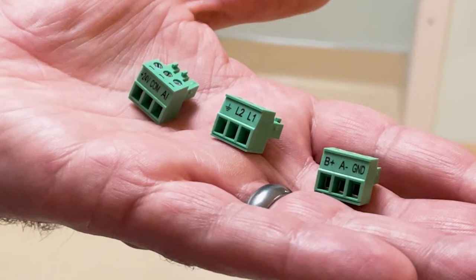The kit comes with removable connectors for the flex monitor. Starting from left to right, you have your analog input to connect the transducer from the ceiling that we installed in the over-the-door box. The L2 L1 is the power connector for power from the original box on the wall. The MSTP connector uses new wiring we pulled because this was a LON device.